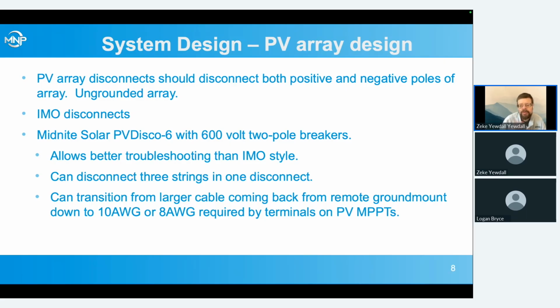So one thing to be aware of is that the PV array disconnects need to disconnect both the positive and the negative poles of the array. And that's because this is an ungrounded floating array. It's actually a lot more sensitive to detecting ground faults if you haven't grounded one of your conductors already. And that's why virtually all of the high voltage string inverters went to that 10 plus years ago.